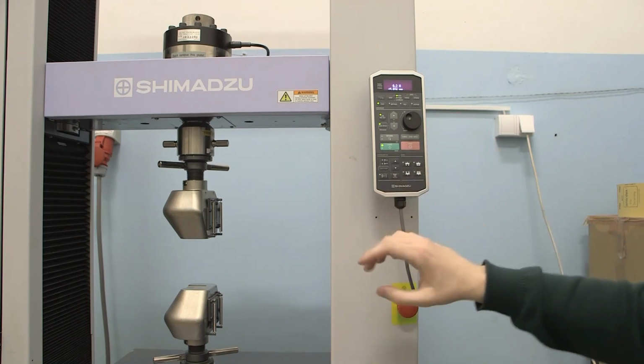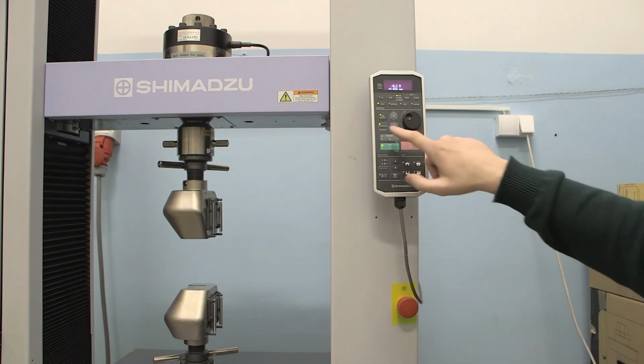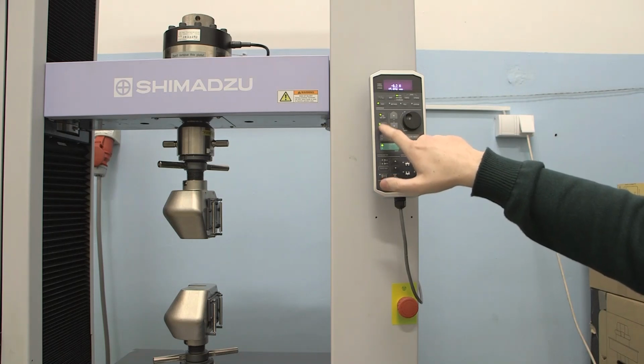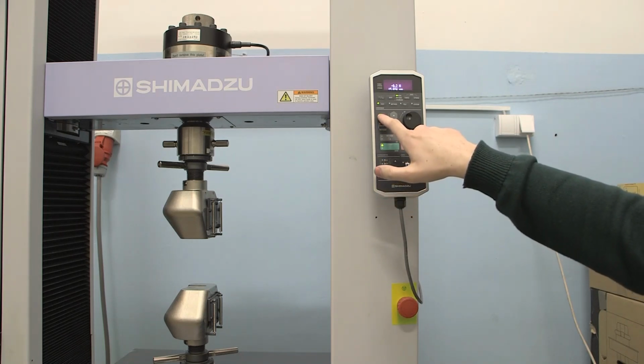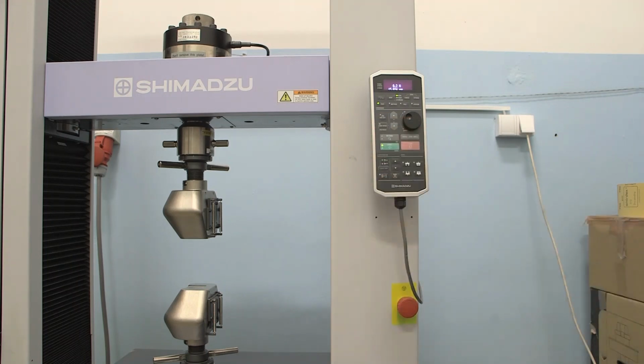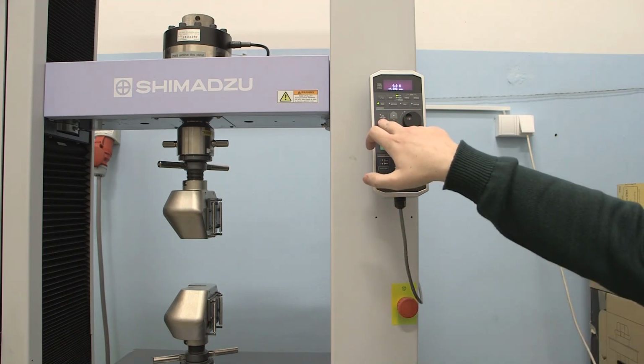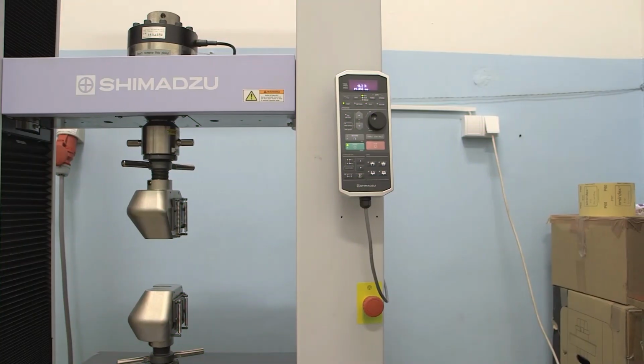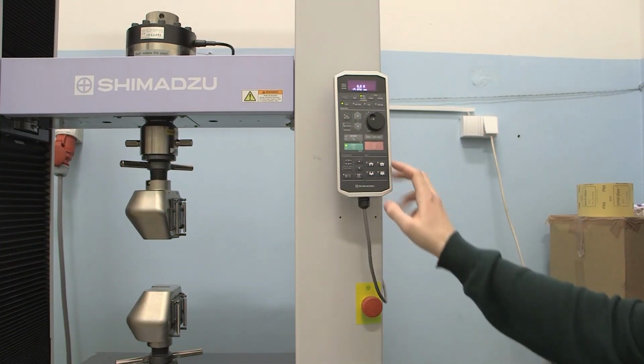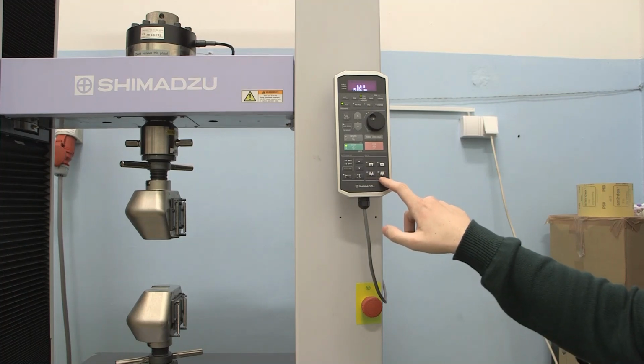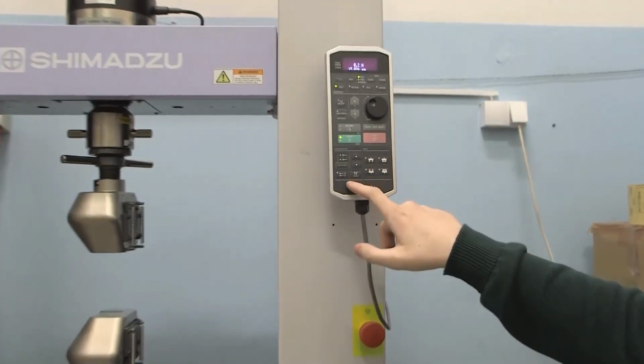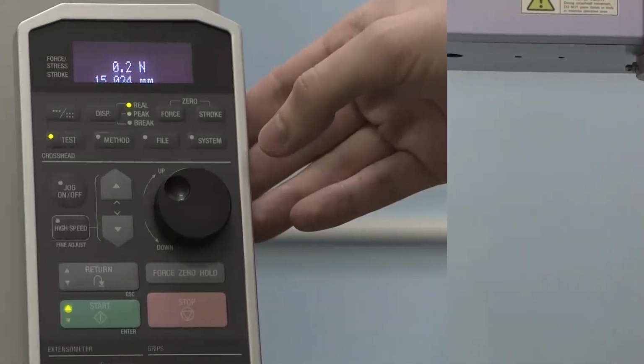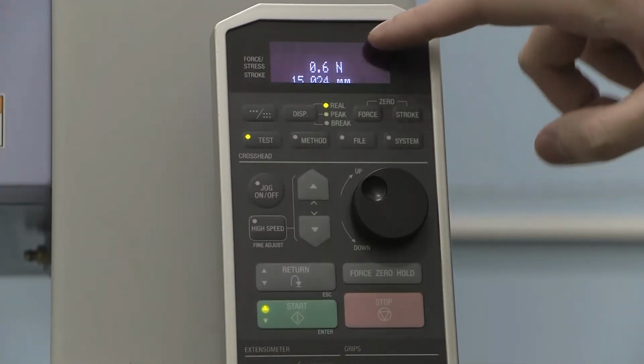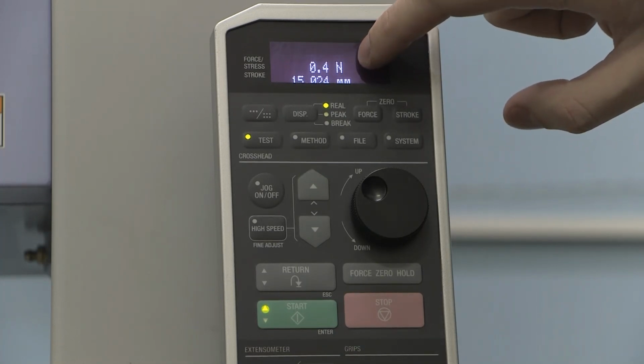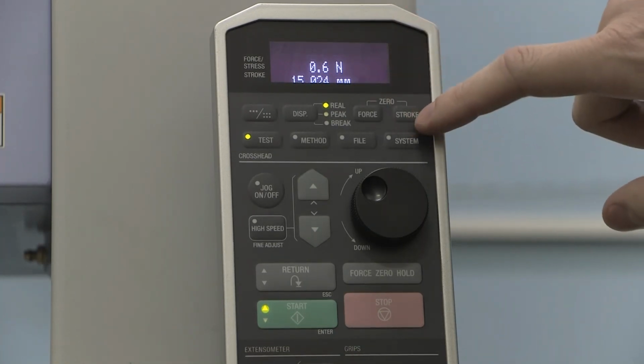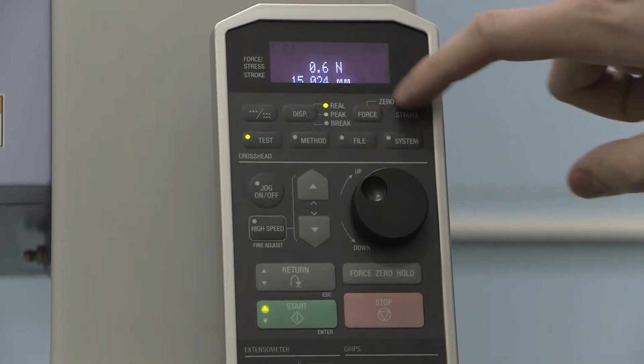Using this jog movement, you insert a specimen into the grips there. So I'll deactivate high speed, and I'm deactivating the jog. When you're finished, you have to deactivate the jog with the on-off button to start your testing. Then you have some options about the shape of your grips, which ones you will use, and so on. Before the testing, if you want to zero the value of force and displacement, you have this small option to zero those values.